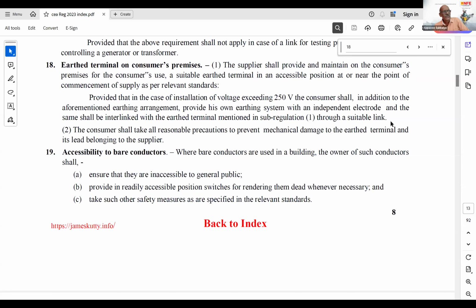Please, sir. Regulation 43 deals with providing residual current devices for all electrical installations. So this is in addition to any... in TNS system, you are not required to provide a residual current device, and automatic disconnection of supply takes care of dealing with the faults. So this is an additional protective measure on top of the fault protection measure to safeguard the installation.